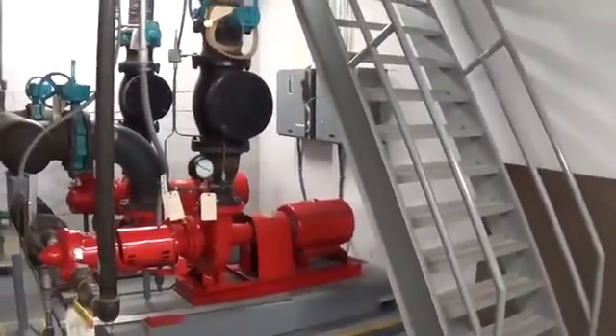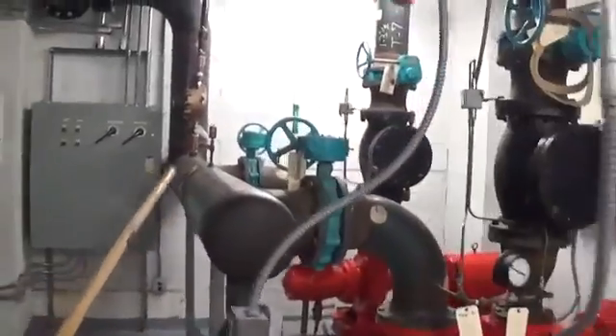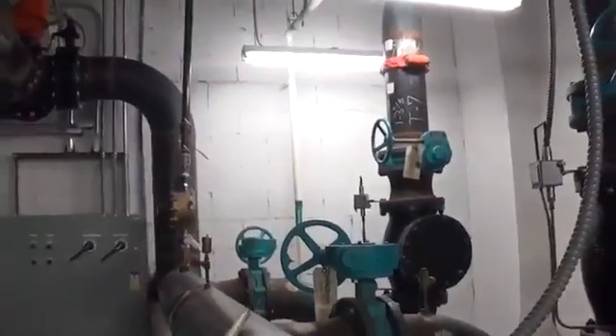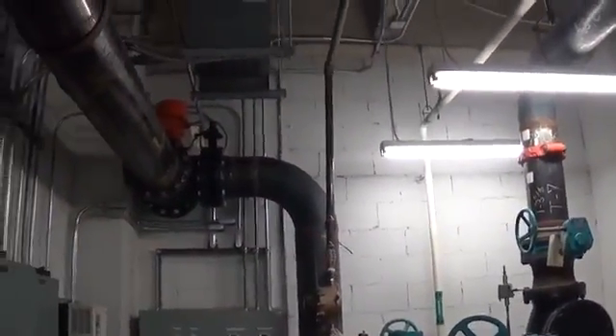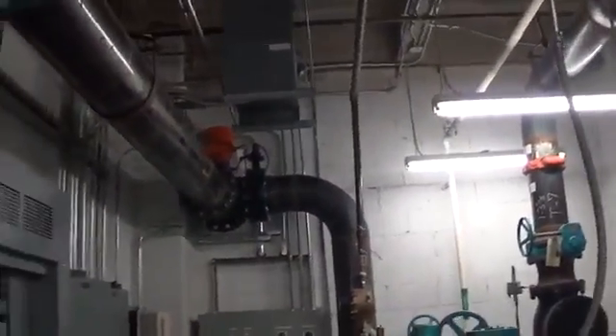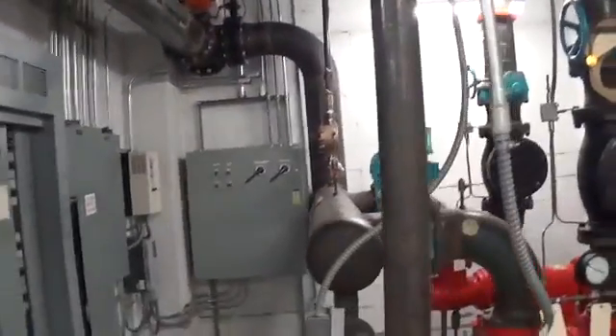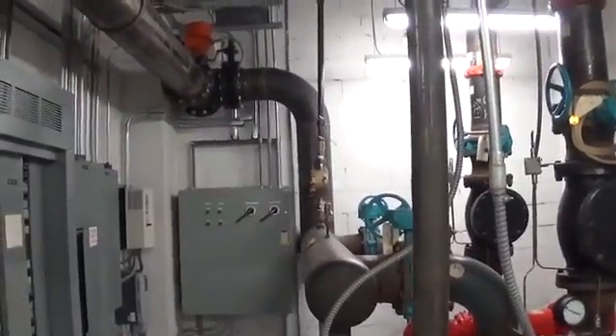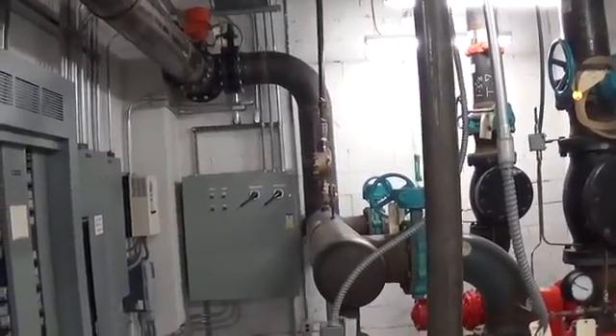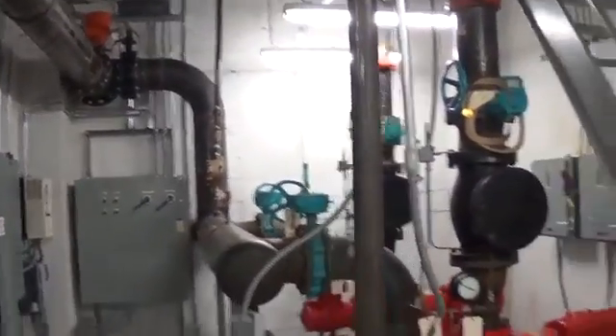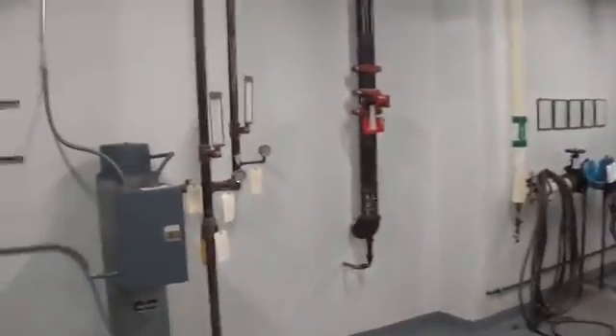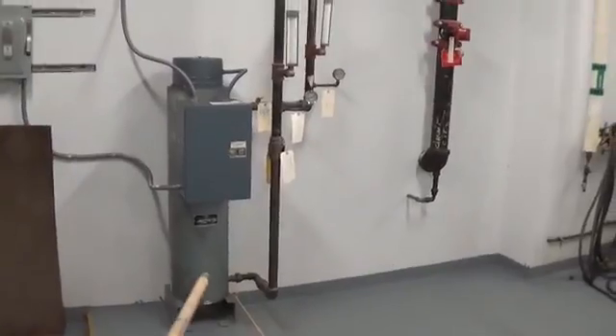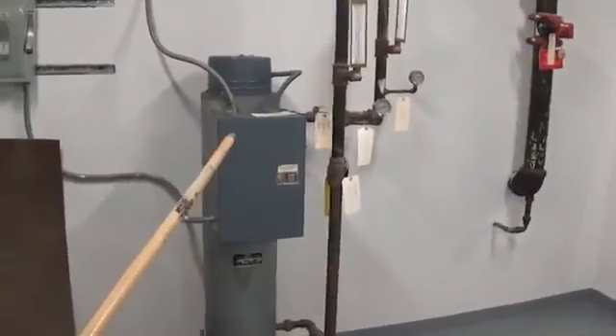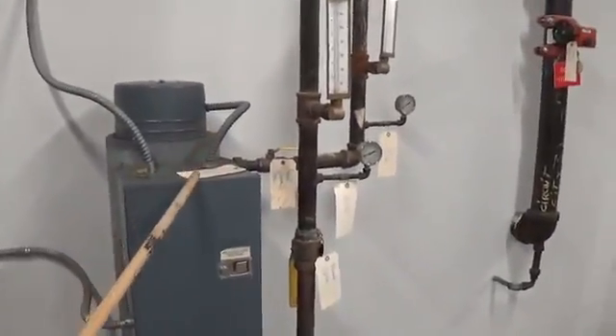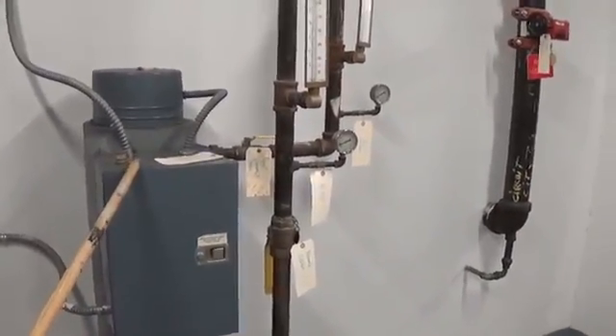It goes to these pumps, and then it leads to outside, where there's a cooling tower sitting on the outside. And the cooling tower is a large reservoir, and it has fans at the top of it, and the fans reject the heat into the atmosphere. We'll take a walk out there. It's kind of dark and cold today, but we'll do the best we can. This is a sump heater, and what this does is it keeps the basin of the cooling tower from freezing solid.